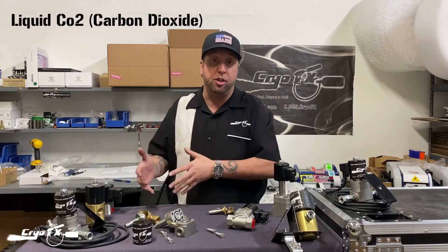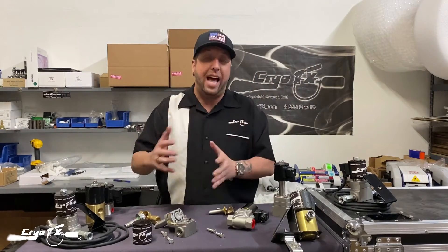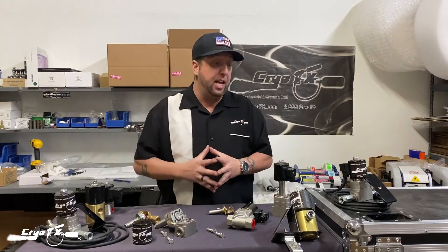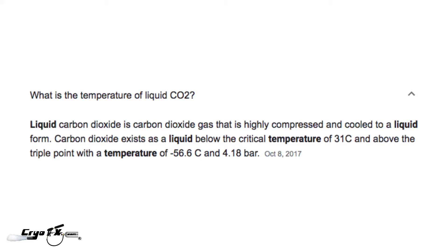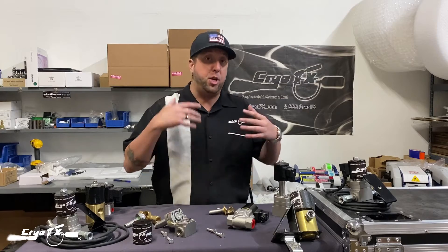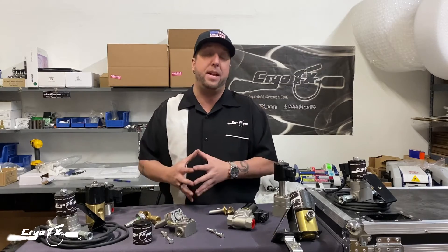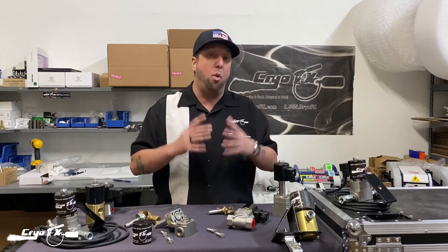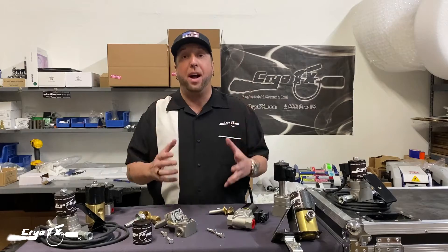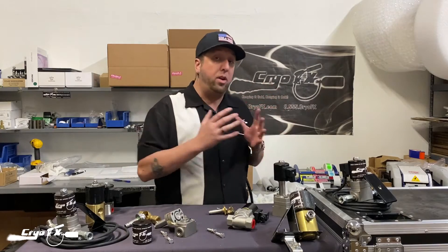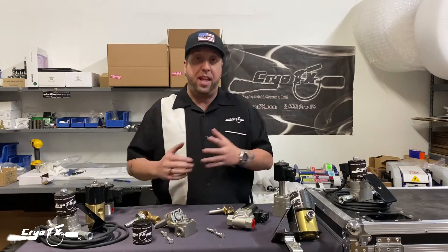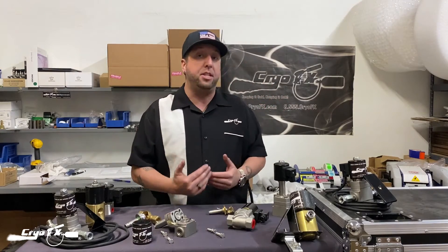This valve specifically deals with liquid CO2. Why does that make a difference? Liquid CO2 runs a lot colder than gaseous CO2. They're both at about the same pressures — anywhere between 800 and 900 PSI. But if you don't get the right valve to handle the right temperatures, you're going to have a problem.